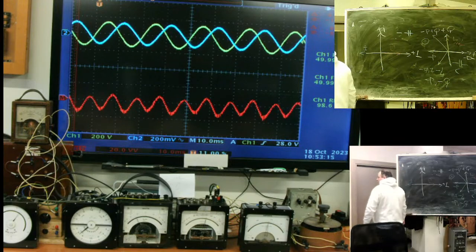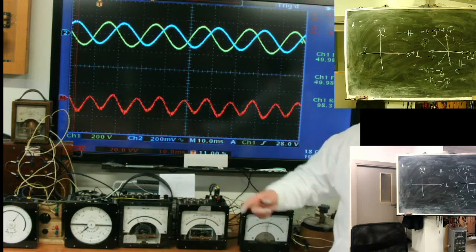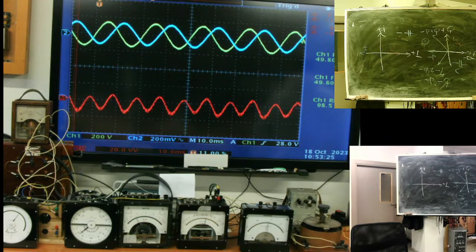Mode when active power goes from us and reactive here. At night, here in Latvia, we have one problem. Capacitance of our 330 kilovolts network is quite large, but reactive load at night is much smaller. And this means that we need to put somewhere the reactive power generated by our high voltage line.